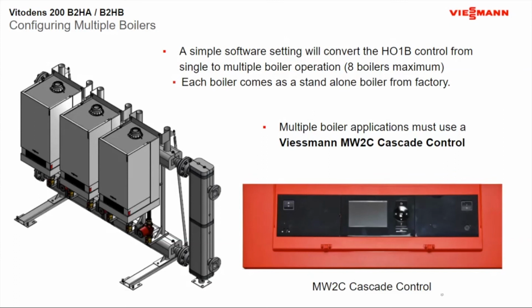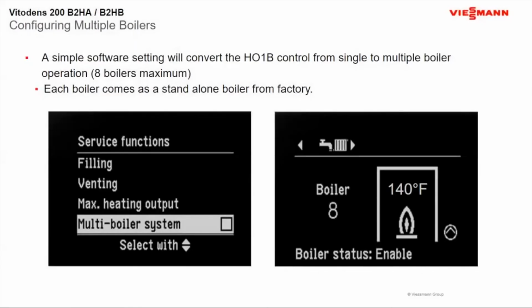The cascade has been changed. As you can see, this is the same exact control that was on the front of the boiler. This has been changed a few years now. Just note, it is now a touchscreen on this part here, which I just set up the other day in our boiler room. So I actually was given a class on how to set up multiple boilers with the cascade control, LON communication, and all of that. So if you're looking to do that, I have that as well.